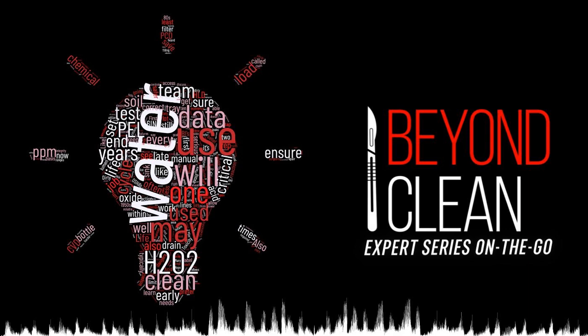There are three critical elements for reducing dried soils inside endoscopes: time, time, and time. The time to start endoscopy pretreatment is immediately after the patient procedure. Scheduling and staffing must account for this vital but time-consuming procedure. Time is not on your side with immediate bedside cleaning.